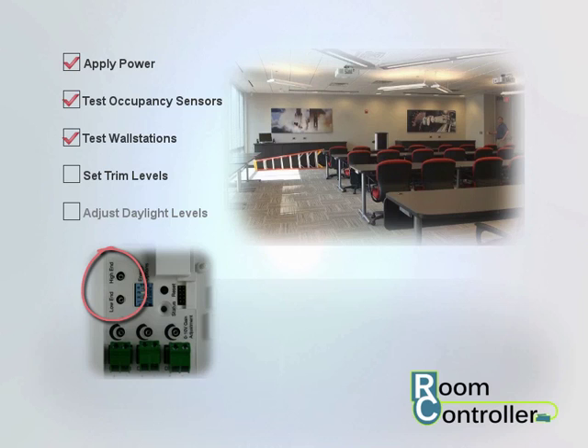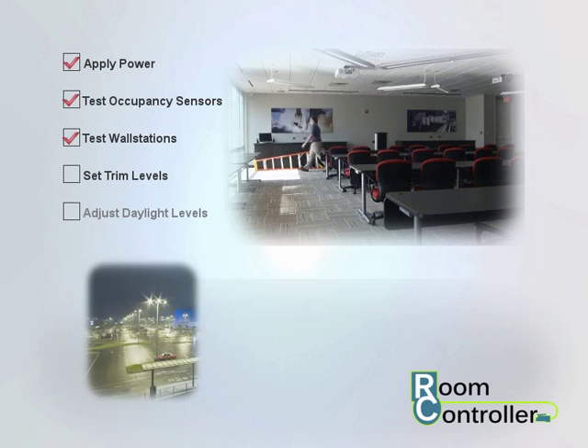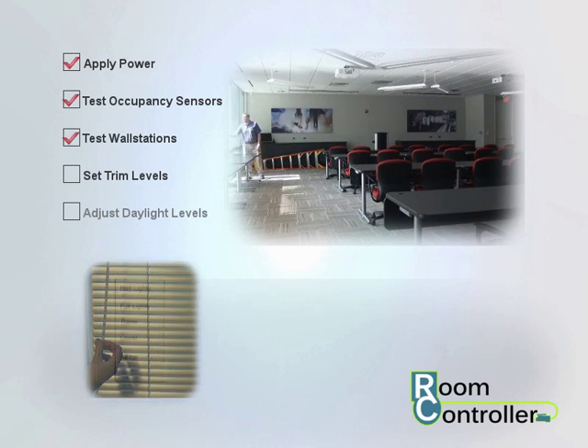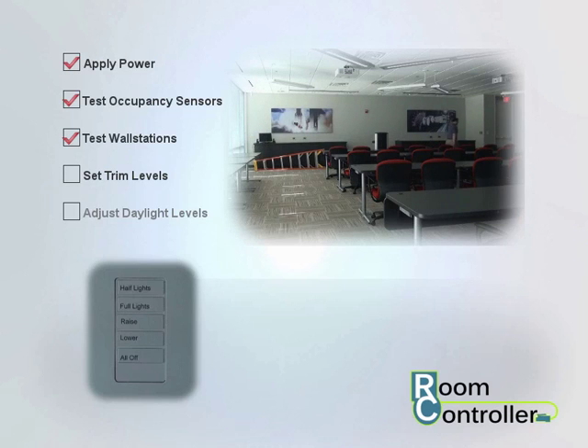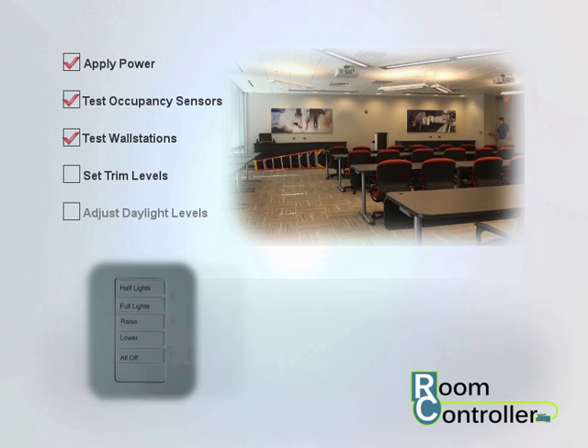Trim level adjustments are done using adjustment dials on board the room controller. For best results, adjust the trim settings at night or during the day using shading to darken the space. Using the wall stations, turn on all controlled lighting. For fluorescent lighting loads, wait 1 minute to allow lamps to warm up.